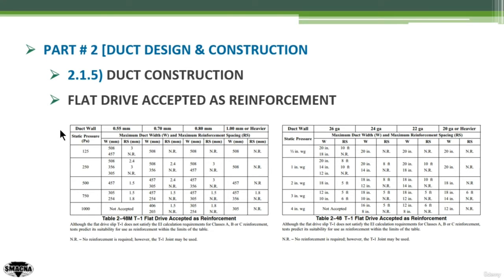Let's look at the table on the left, which is in SI units. This table has two divisions. The first division represents the static pressure in Pascal for the duct operating system, shown in the first column. The second is the first row, which refers to the duct wall thickness: 0.55 mm, 0.7 mm, 0.8 mm, and 1 mm or heavier.